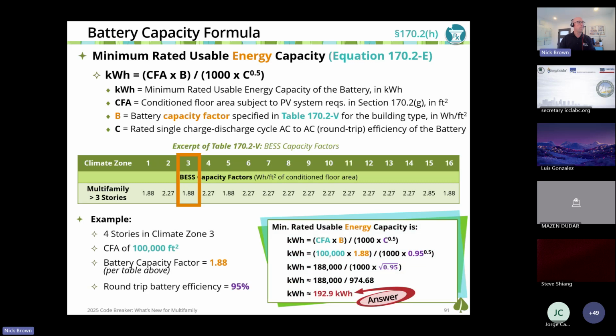Let's do an example. 4 stories, climate zone 3, so our factor's 1.88. We've got a 100,000 square foot building, 95% round trip efficiency. You see that gives us a 193 kilowatt hour requirement. That's the energy capacity measured in kWh.